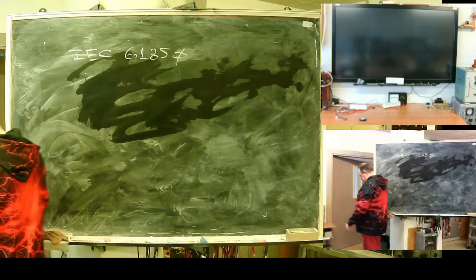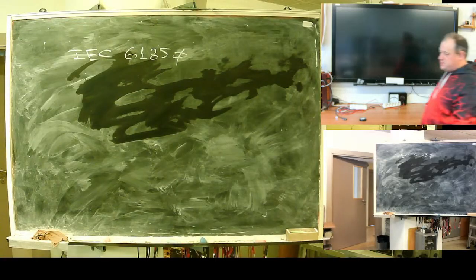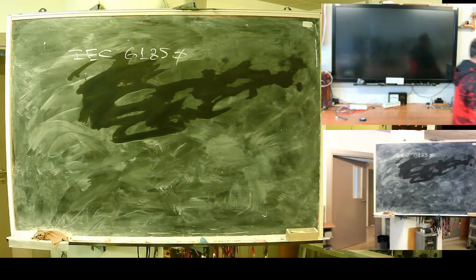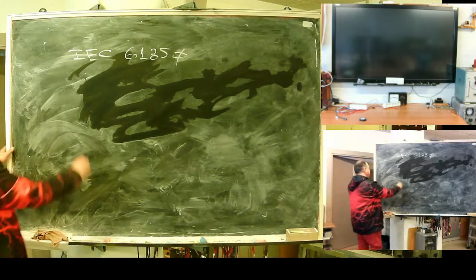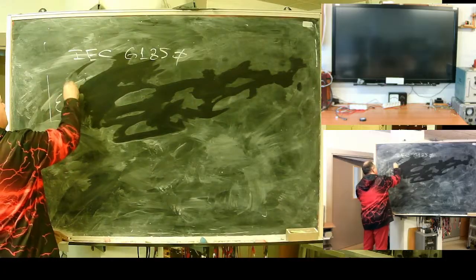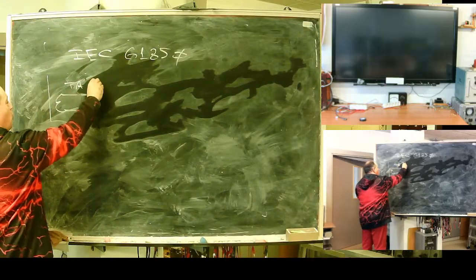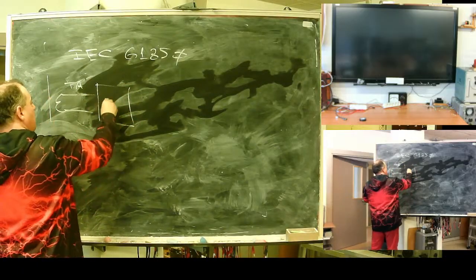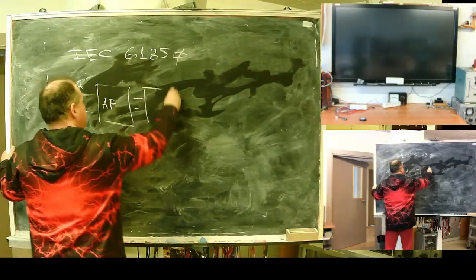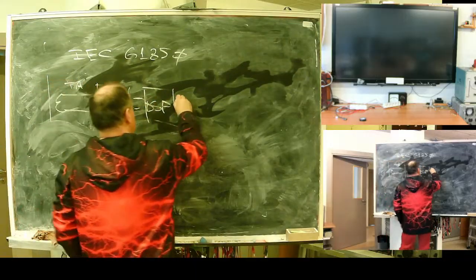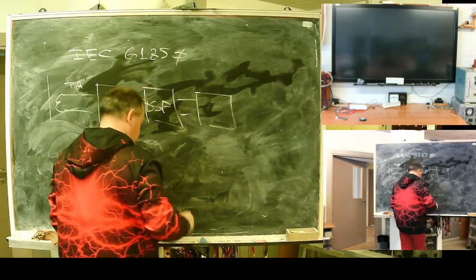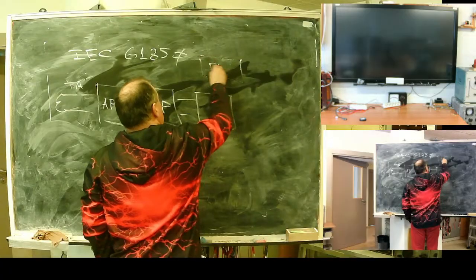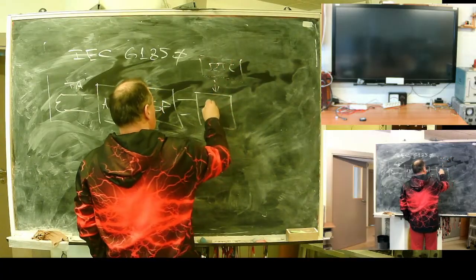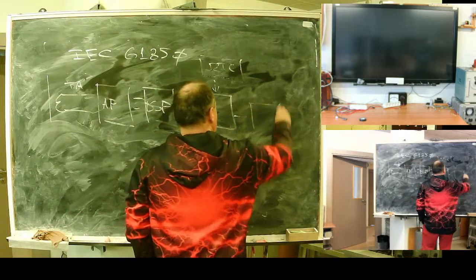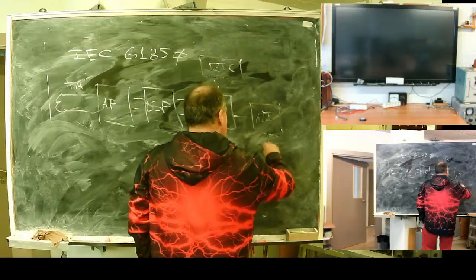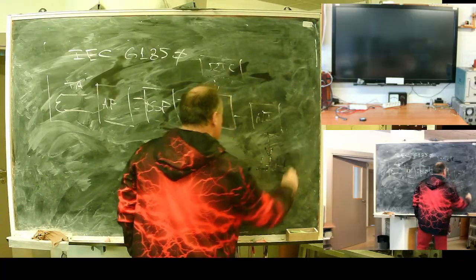IEC 61850, it's a standard framework for digital substations. In the case of a digital substation, things are done a bit differently. We have a current transformer, and it already comes with analog processing, DSP, RTC, and logic, and a network interface, connected to the substation LAN.